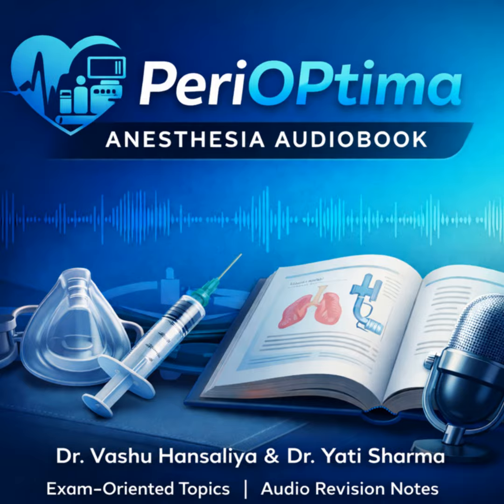And the second, more acute failure. An incompetent unidirectional valve that's stuck open. This is lethal. Gas just flows back and forth between the patient and the reservoir bag, completely bypassing the absorber. The CO2 level builds up incredibly fast. The clinical consequence is acute, severe respiratory acidosis and hypercapnia. How do you spot that? You have to visually check the dome of the valves. They should flutter or move, confirming they're working. If they're not moving, that's a massive red flag.